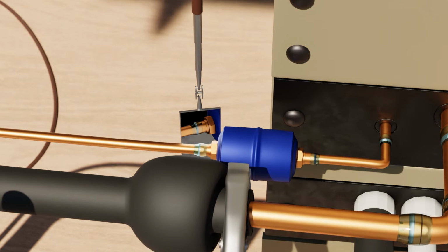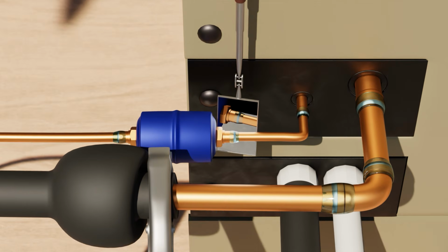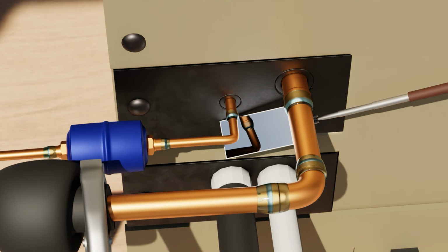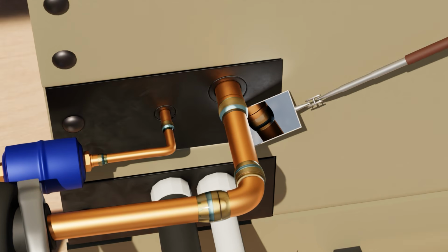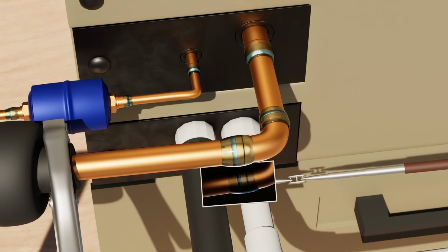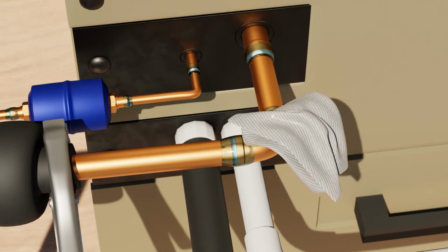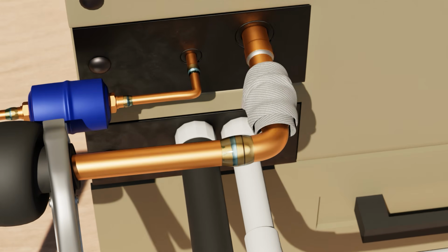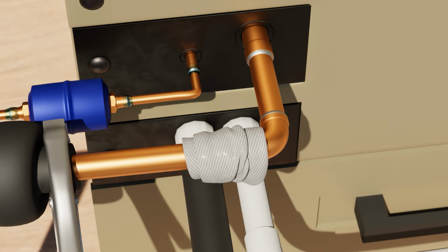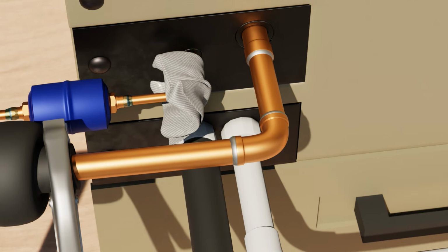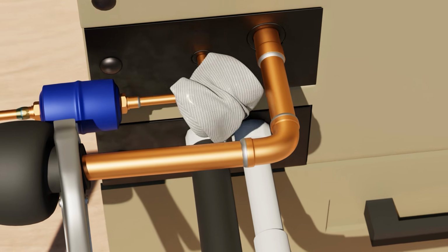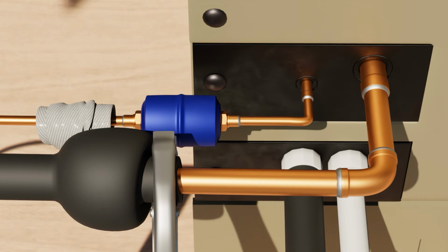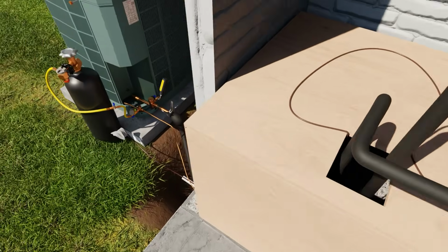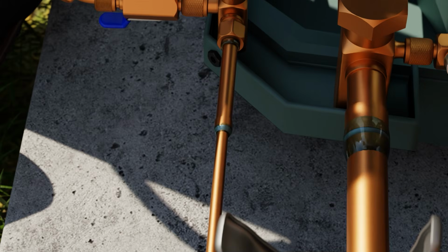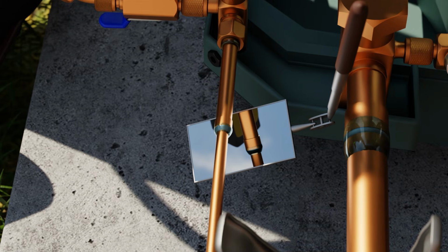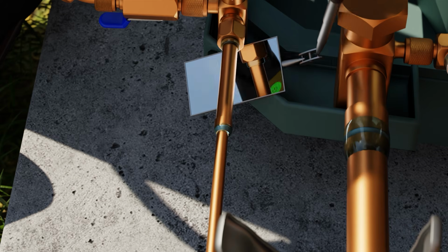Keep in mind, if you have a hard shut-off TXV, the pressures will become unbalanced on the high side and low side once you hit around that 250 psi number in some conditions. A hard shutoff TXV, an HSO, often called a non-bleed expansion valve, will make the pressures become imbalanced on the high and low side once you hit a particular point. So in some cases, in order to hold a fixed pressure on both sides, you need to actually allow it to equalize through the gauges.